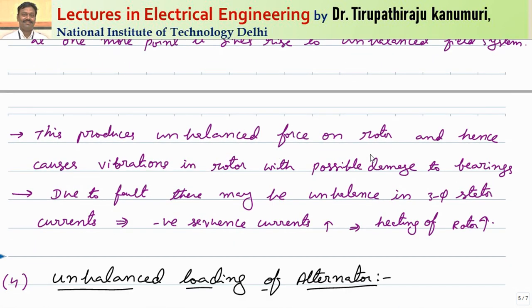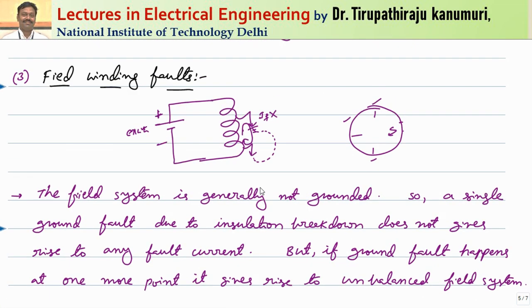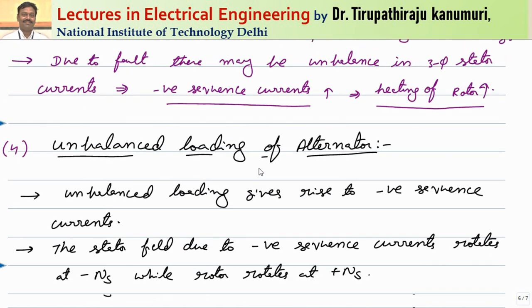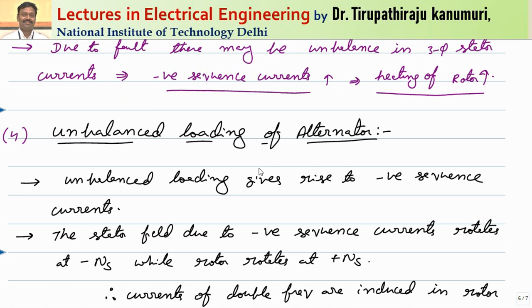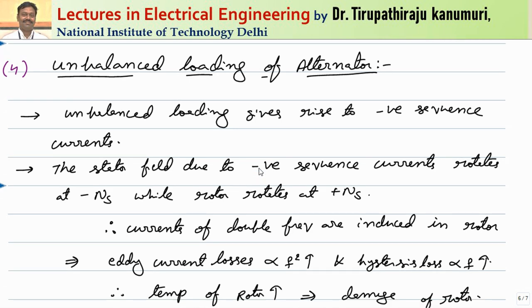Because the field distribution is not uniform, the EMF induced in different phases of the stator is not uniform, producing unbalanced currents in the three-phase stator circuits. These unbalanced currents can be resolved into positive, negative, and zero sequence components. The negative sequence component leads to heating of the rotor. To summarize: a single ground fault in the field circuit does not create any problem, but more than one ground fault creates negative sequence components and vibrations in the rotor, which is very dangerous and should be isolated immediately.